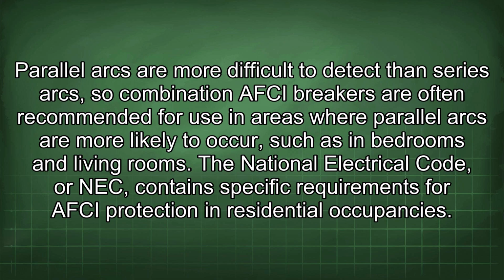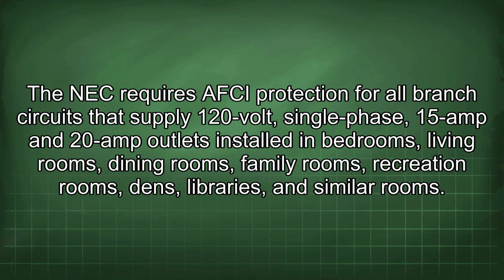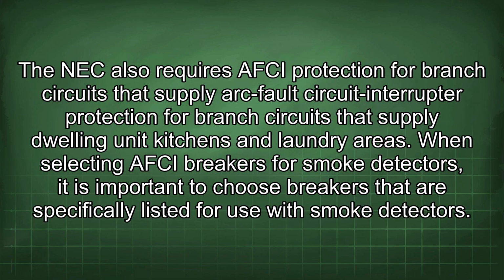The National Electrical Code, or NEC, contains specific requirements for AFCI protection in residential occupancies. The NEC requires AFCI protection for all branch circuits that supply 120-volt single-phase 15 amp and 20 amp outlets installed in bedrooms, living rooms, dining rooms, family rooms, recreation rooms, dens, libraries, and similar rooms. The NEC also requires AFCI protection for branch circuits that supply dwelling unit kitchens and laundry areas.